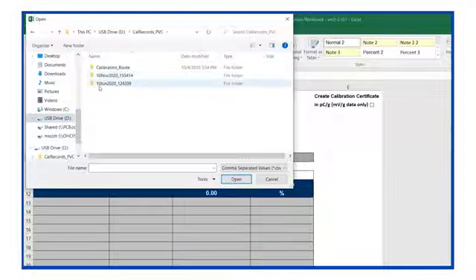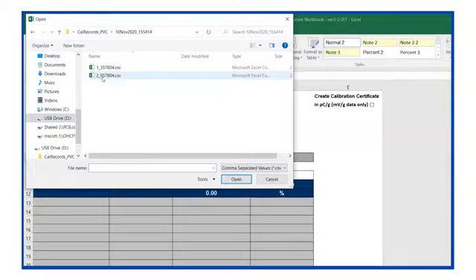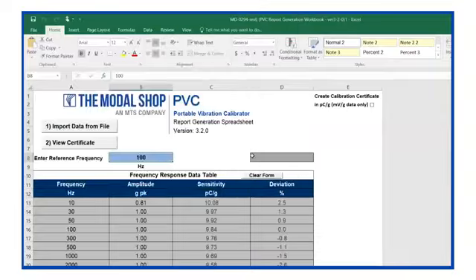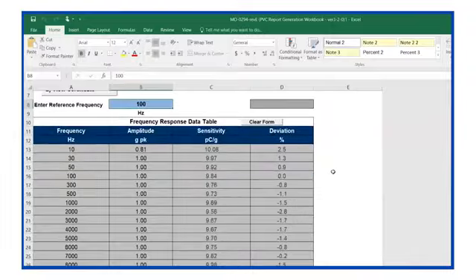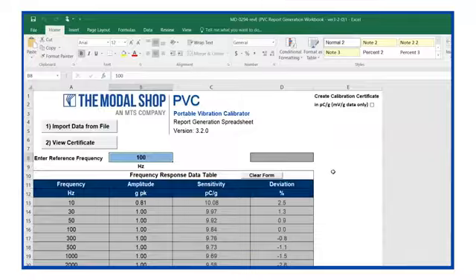CalRecords_PVC, choose the date and time on which you exported the file, and then choose the file. Now my raw data has imported into this data table, but this is not the calibration certificate. My reference frequency is set for 100 Hertz, but I can change that if I'd like. The key is to make sure you take data at the reference frequency. In this case, 100 Hertz is correct, but it can be changed to 159 or 80 or whatever you'd like.